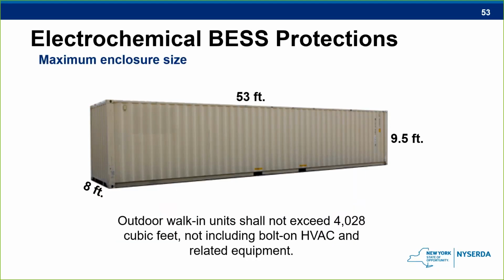I touched on these outdoor walk-in units a little bit before, but they also have volume limitations. They cannot exceed 4,028 cubic feet, and the dimensions you see above it are like a rough estimate of what that might look like. Any container that's larger than this would cause the system to be treated as an indoor installation, which would have stricter requirements. And as the energy density of batteries continues to go up as the technology evolves, first responders should be aware that a lot of energy would be stored inside one of these containers.